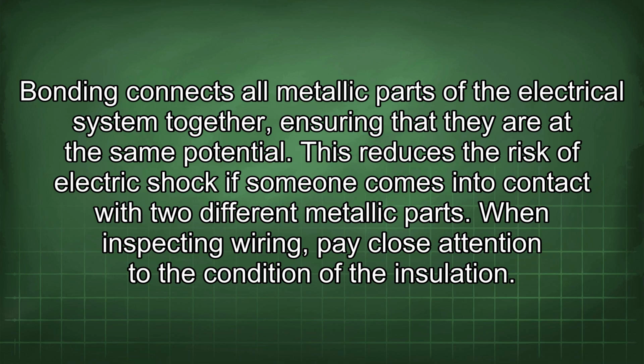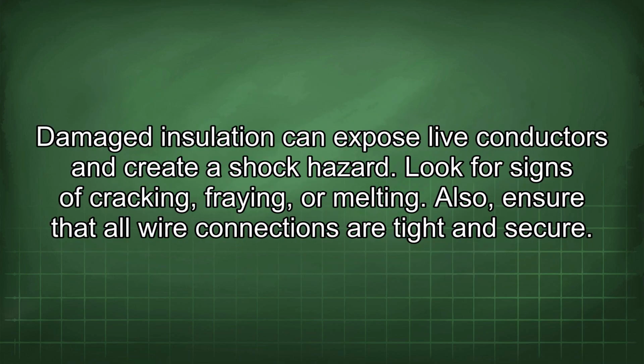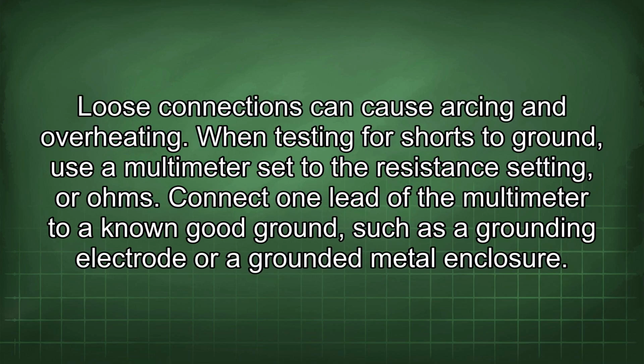When inspecting wiring, pay close attention to the condition of the insulation. Damaged insulation can expose live conductors and create a shock hazard. Look for signs of cracking, fraying, or melting. Also, ensure that all wire connections are tight and secure. Loose connections can cause arcing and overheating.